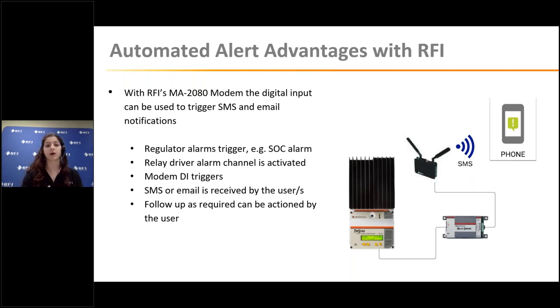Depending on how you've customized your relay driver, how you've programmed it, and what aspects you've asked it to monitor or alarm on, it takes that signal and sends it out through its alarm channels, its digital output channels. It's then able to activate that relay circuit in our universal hub. Depending on how you've programmed your universal hub, it can send out either an SMS or an email with a message to any desired contact.